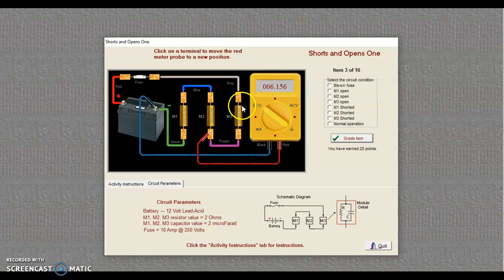Let's come here. Okay. So I saw a load drop in M3. I know that M1 or M2 is possibly shorted in this situation. So let's get on the other side of M2. Okay. And so we see no change right there. And what that's telling me is M1 is good and M3 is good. M2 is shorted.